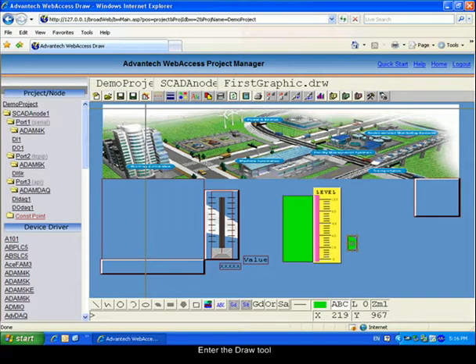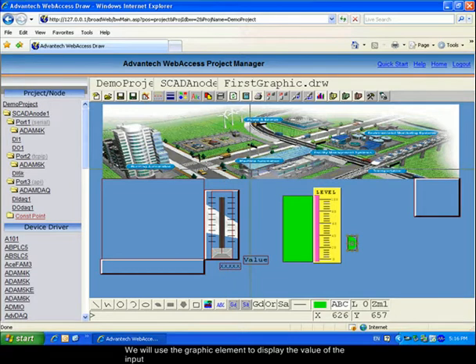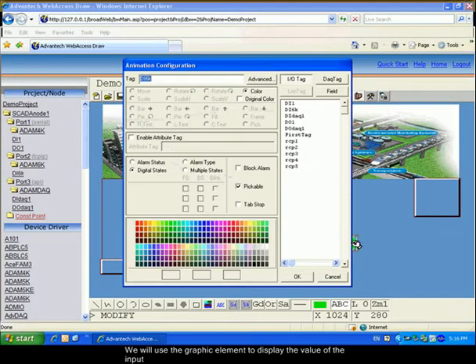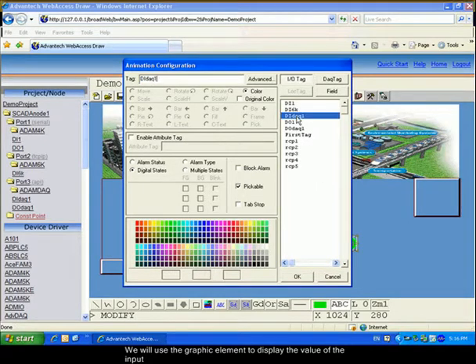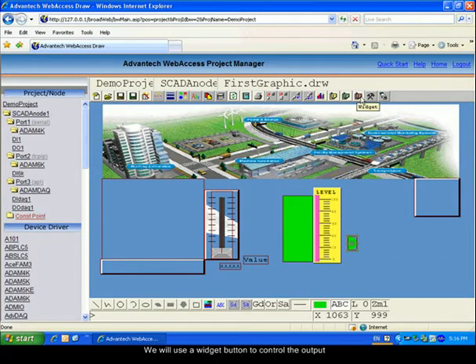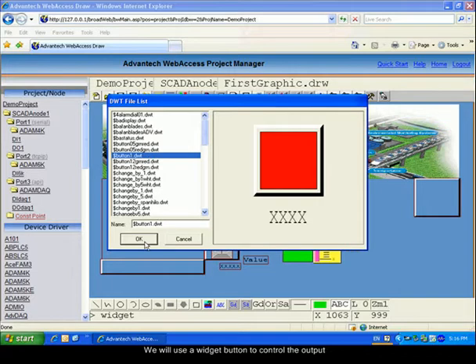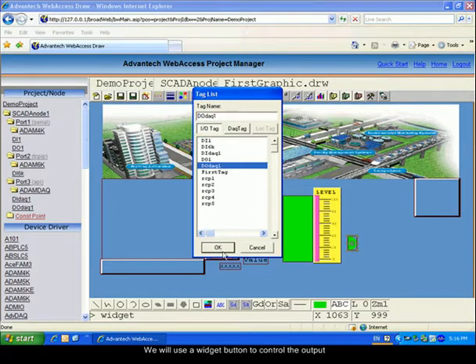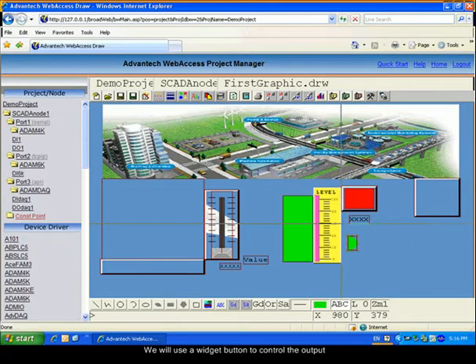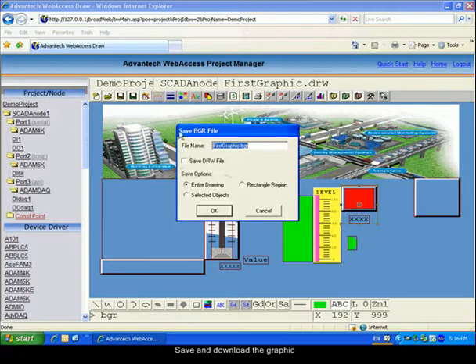We will use the graphic element to display the value of the digital input. Enter its properties and change the associated tag. Then we will add a widget button to control the output. Select the output tag and place the button. Now save and download the graphic.